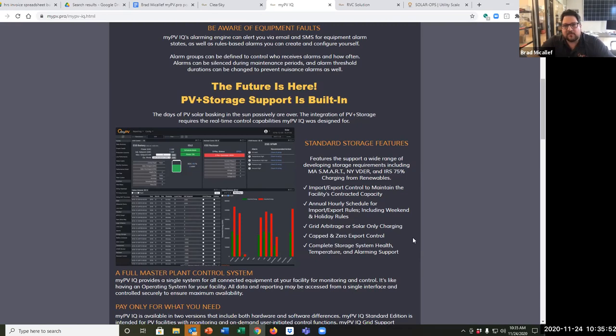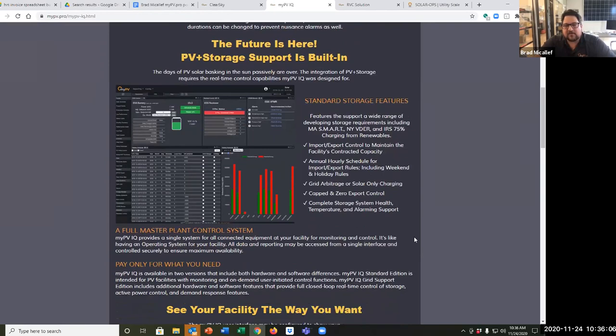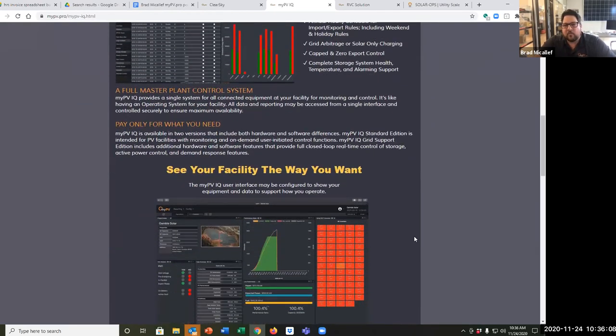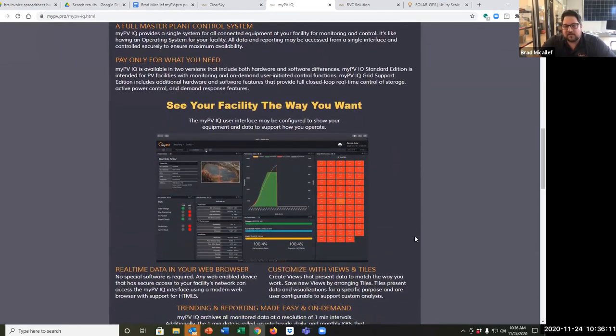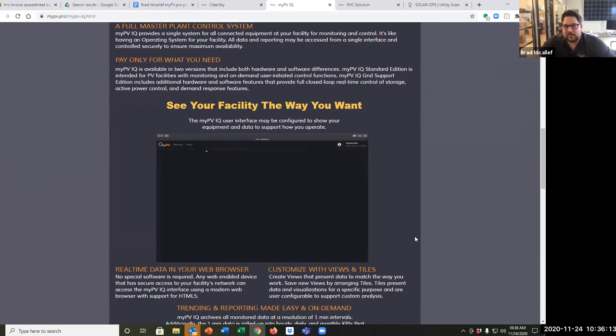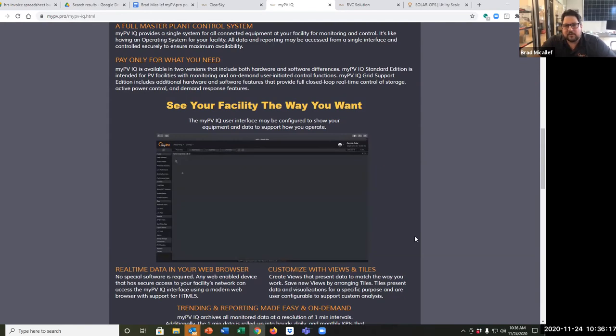This is designed to be a hybrid of what we'd typically think of as monitoring, which is very easy to use, and SCADA, which traditionally is harder and expensive. We bring what we feel is the best of a monitoring package from an ease of use standpoint, with some SCADA features, things to control that recloser, open, close, and trip and reset, remotely.